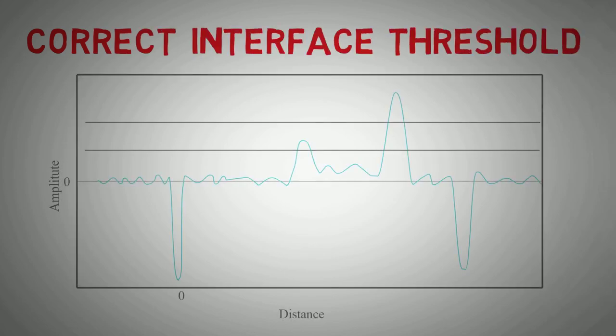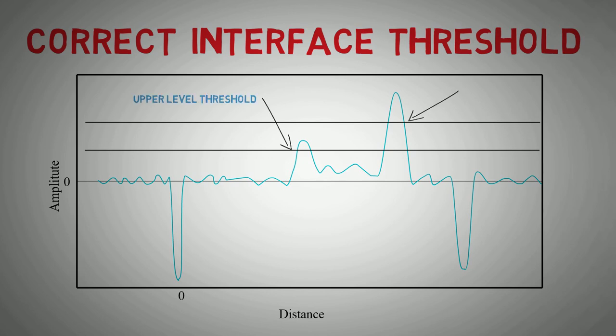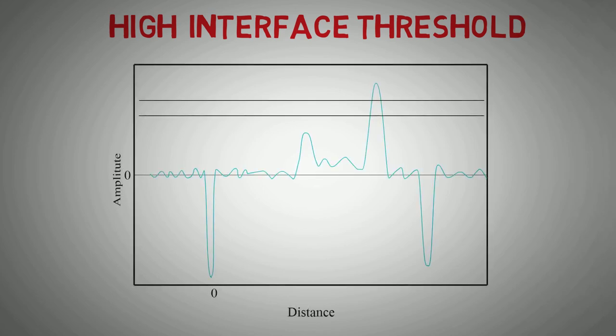Interface level setups require two threshold settings to determine between the two distinct reflections. Here we can see a correctly set threshold for an interface setup. If the threshold is set too high, an interface level may indicate as the upper or bulk level instead of the desired interface reading.